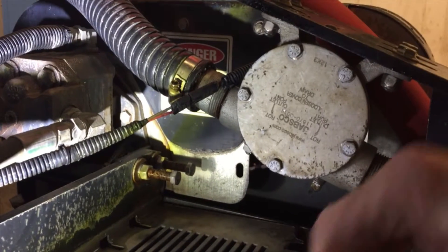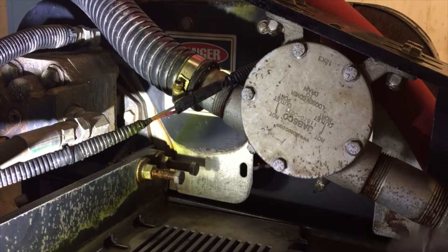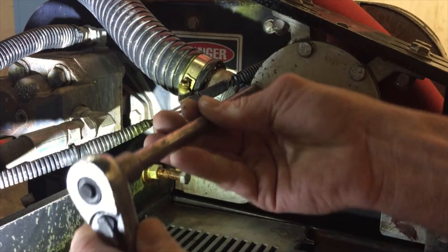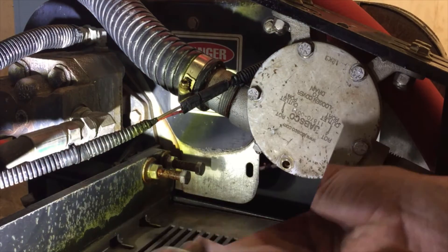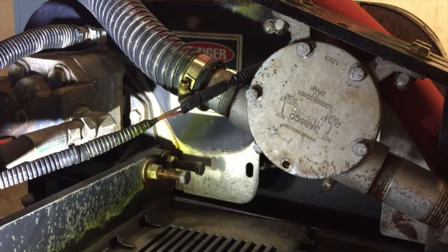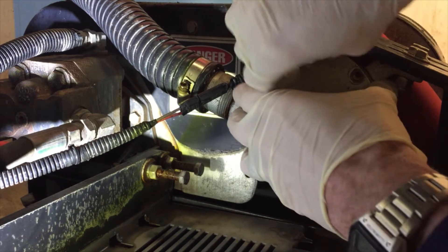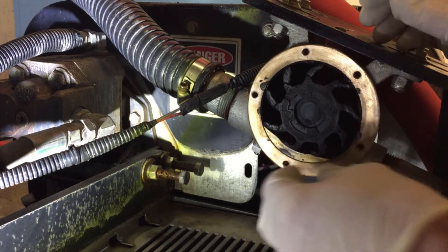Our old 500 actually has some flathead screws but this one just has bolts, so I'll loosen these. We've got five of them here — it's a 7/16 deep socket. This plate here is kind of upside down, so we need to note that these bolt holes have to be lined up properly. There is a gasket, so you've got to be careful. Let's note which way it spins because that's also important.